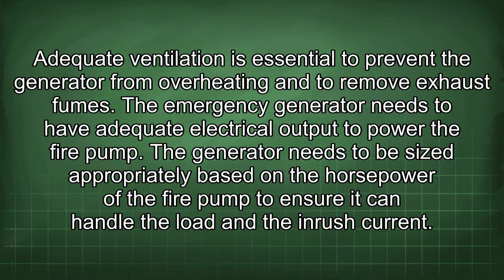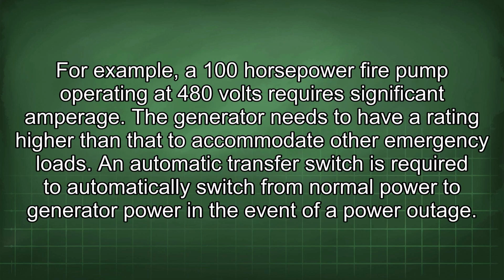The emergency generator needs to have adequate electrical output to power the fire pump. The generator needs to be sized appropriately based on the horsepower of the fire pump to ensure it can handle the load and the inrush current. For example, a 100 horsepower fire pump operating at 480 volts requires significant amperage. The generator needs to have a rating higher than that to accommodate other emergency loads.